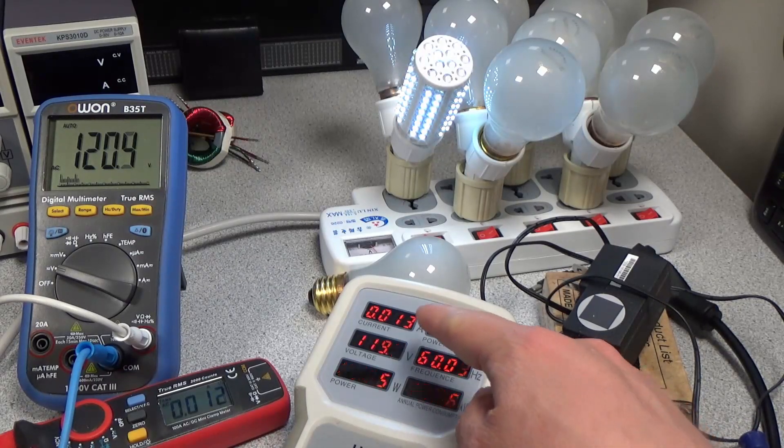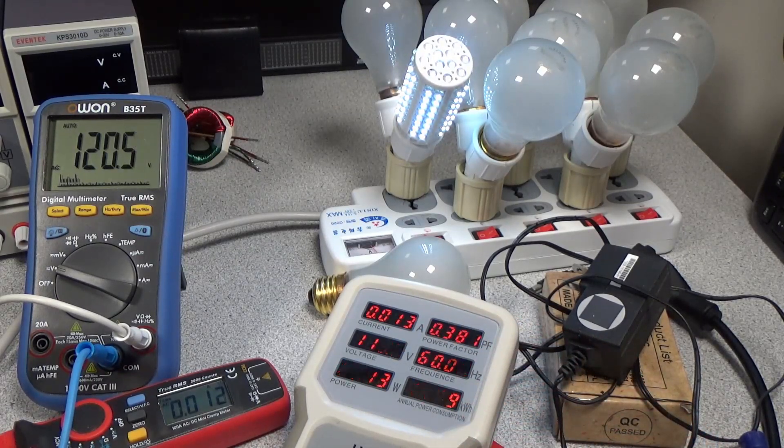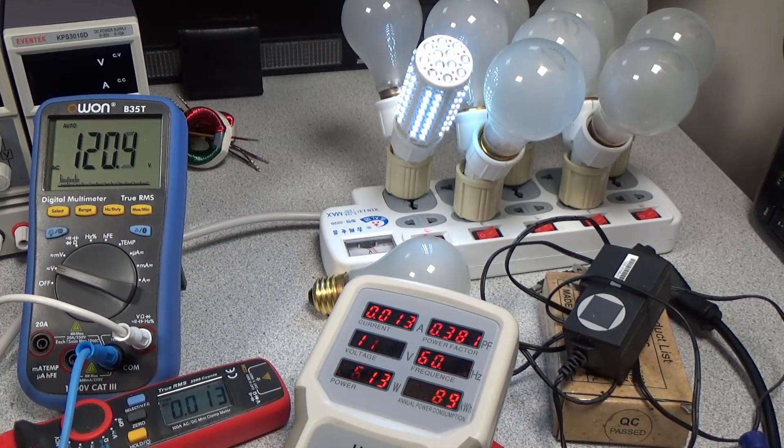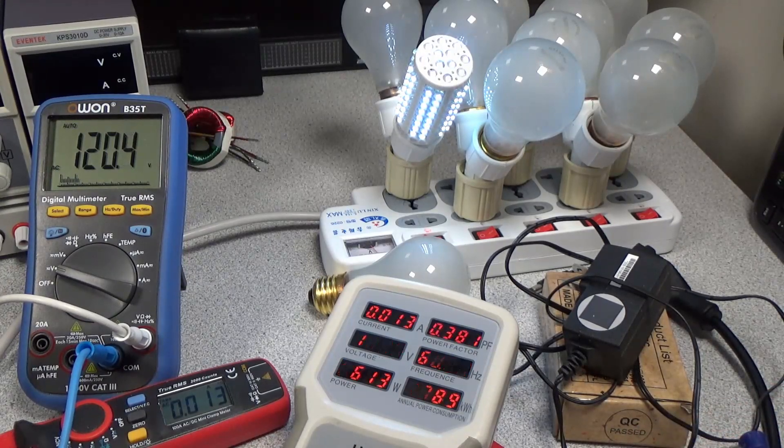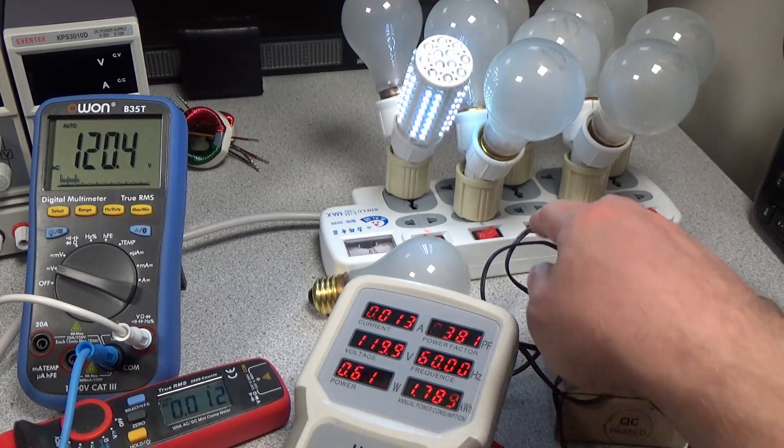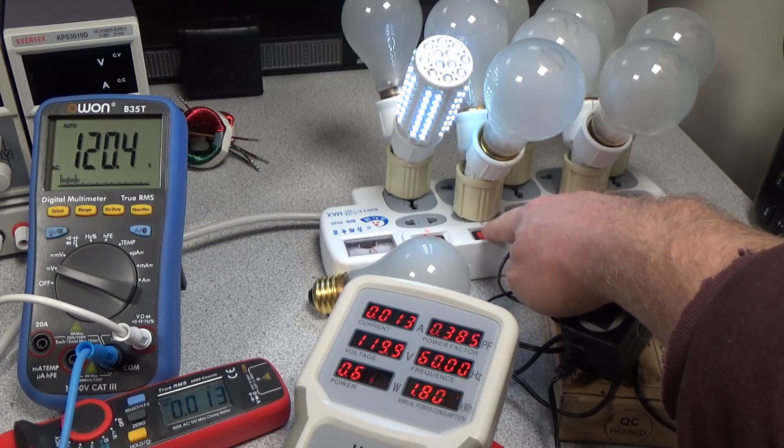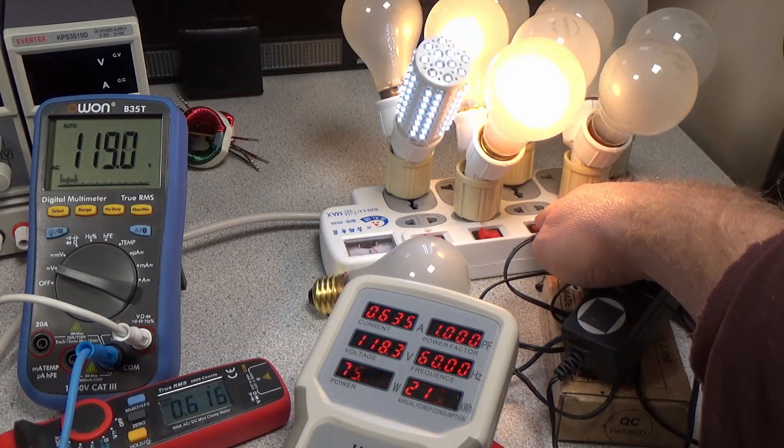Even if you just do the math on what it's showing for power factor, current, and the watts, it doesn't line up with itself. So this already shows that this meter is kind of out of its comfort zone.